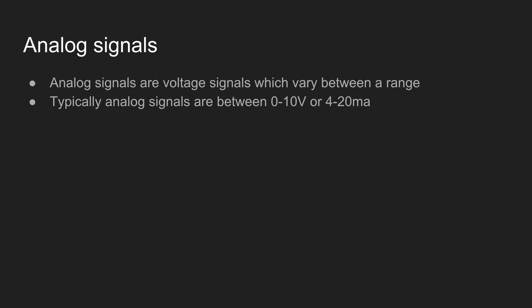In some cases you may come across some PLCs in the field which only support 0 to 10 volt ranges and not 4 to 20 milliamp ranges. Whereas your sensors may only support 4 to 20 milliamp signals, you may need to do some conversion from 0 to 10 volt to 4 to 20 milliamp ranges.